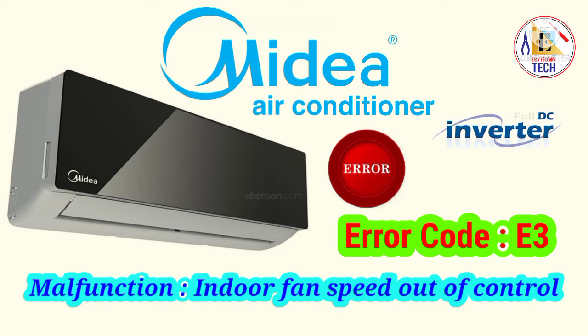When you see the error E3, it means indoor fan speed out of control. This happens due to the output supply from our PCB. If it is not good to the fan motor, at that time you can get this error E3. Or sometimes if our fan motor is not operating properly, at that time also it can show the error E3. The main cause in this is the indoor PCB or the fan motor.